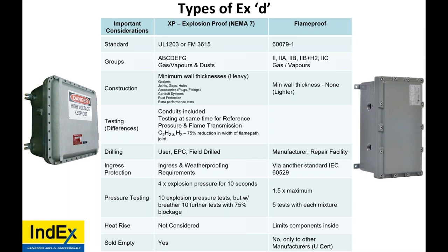Explosion proof boxes, you can put anything you want into them, almost, as long as you follow the manufacturer's requirements. Flame proof, what comes in it is the only thing you can accept. You cannot change any part unless it's like for like: same make, same model, same certification as per the certificate and the manufacturer's IOMs.